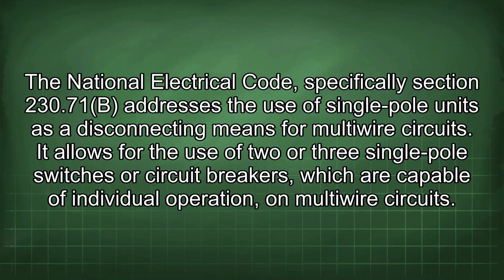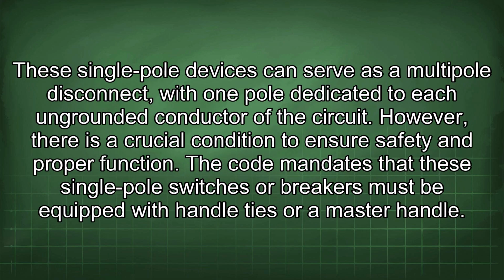The National Electrical Code, specifically Section 230.71(B), addresses the use of single-pole units as a disconnecting means for multi-wire circuits. It allows for the use of two or three single-pole switches or circuit breakers, which are capable of individual operation on multi-wire circuits. These single-pole devices can serve as a multi-pole disconnect, with one pole dedicated to each ungrounded conductor of the circuit. However, there is a crucial condition to ensure safety and proper function.